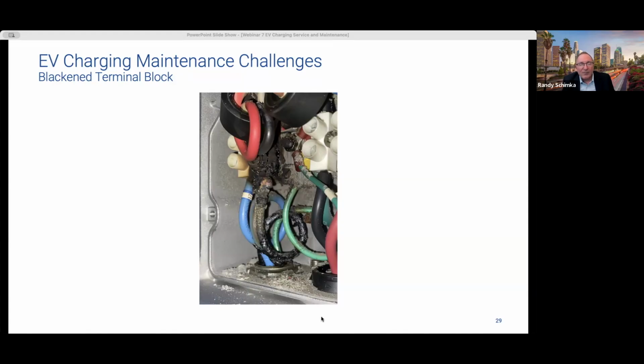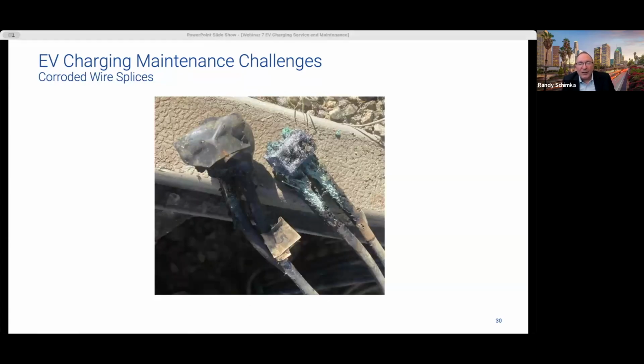In this photo, we see wire splices that are green and heavily corroded, and they're wrapped only in black electrical tape. So corrosion from moisture exposure weakens the connections, increasing the resistance and the fire risk there. Electrical tape isn't really waterproof and it doesn't really meet code for splice protection. So you should use weatherproof splice enclosures or connectors that are rated for the environment and ensure proper sealing to prevent moisture from getting into the splice.